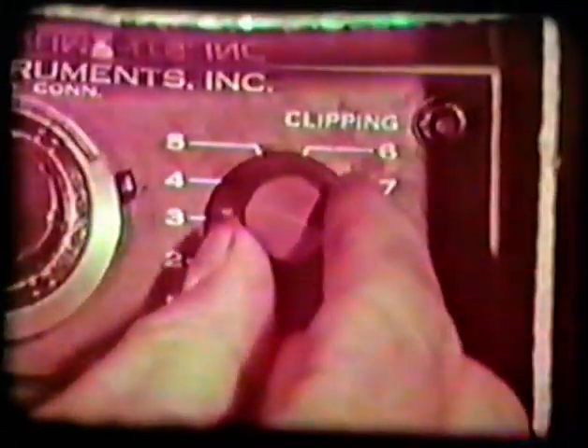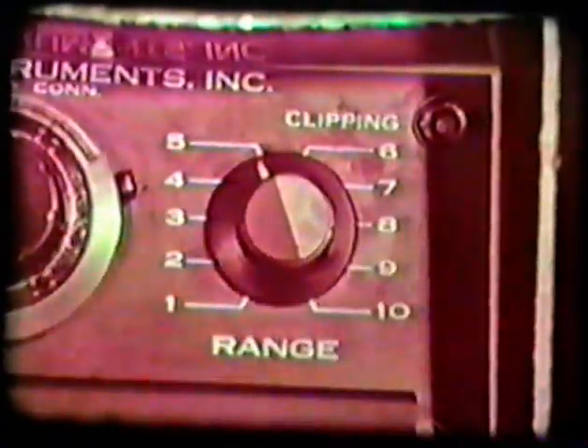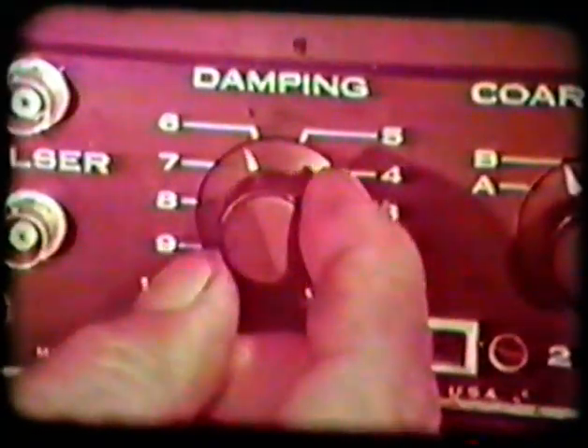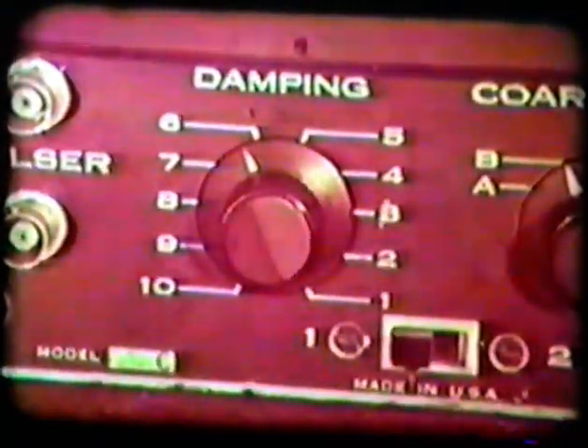Use the appropriate controls to obtain the best possible signal resolution. The gain control allows adjustment in the height of the trace. With the range control, you can stretch out the horizontal placement of the signals. The pulse energy or damping control varies the transmitted power. For best resolution, use the lowest power possible. Some equipment may use the reject control to get rid of grass or extraneous signals. The horizontal lines on the scope face help you estimate percent of bond. As an additional aid, some scopes have numbers at the edge of the screen.